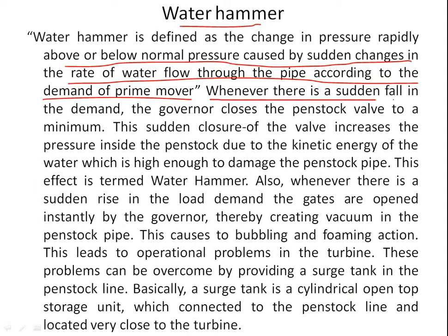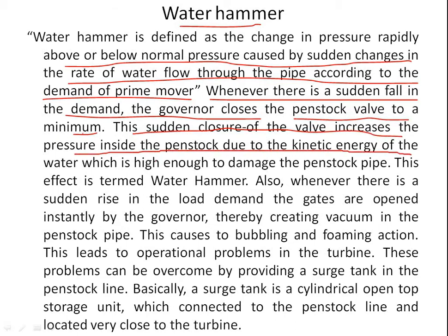Whenever there is a sudden fall in the demand, the governor closes the penstock valve to a minimum. This sudden closure of the valve increases the pressure inside the penstock due to the kinetic energy of the water, which is high enough to damage the penstock pipe. This effect is termed water hammer.